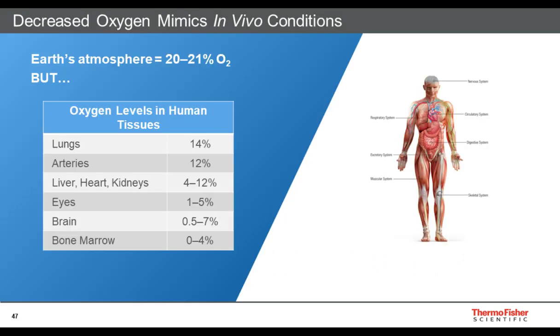So one final note on gas and atmosphere in the incubator: many of us are also using hypoxia in an incubator. The point of this is to decrease the oxygen concentration to mimic what's going on in the human body. The oxygen concentration in the Earth's atmosphere is between 20 and 21%. So if you're listening to me from Melbourne, Australia, it might be closer to 21% because you're at sea level. If you're in Basel in Switzerland, it might be a little bit less oxygen as you get higher altitudes, so that would be closer to 20%.